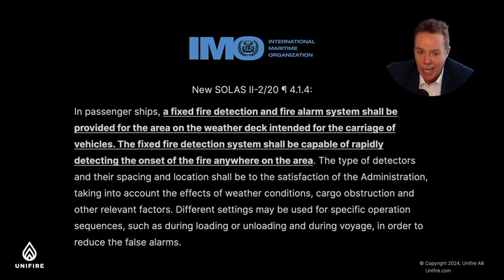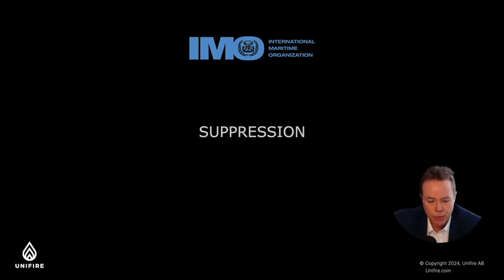So the regulations allow for that use, but again, looking at the LASH FIRE study, which did in-depth research on a number of thermal imaging camera systems, a number of different flame detection systems, and other detectors, and again, I can provide the report, it's clear that the recommendation is that flame detectors be used.